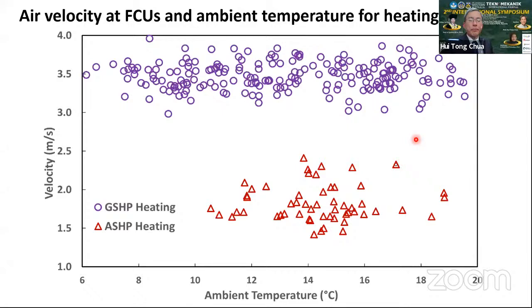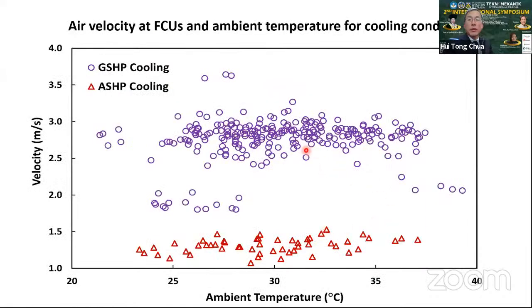And this is correlated well against the air velocity measurement at the fan coil units. For the heating condition, you can see that the airflow rate, which is correlated against the higher velocity of the ground source heat pump, is certainly significantly higher than that of the air source heat pump. This is for the heating condition, and the same applies to the cooling conditions consistently, registering a higher airflow rate.